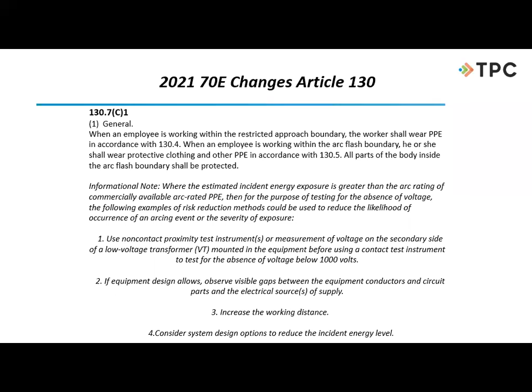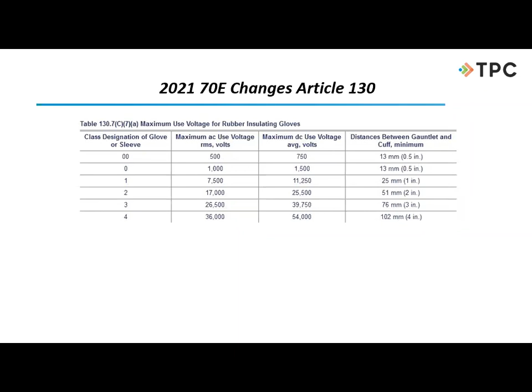They did revise our table on rubber gloves. They gave us, depending on the class of glove, whether it's a 00, 1, or 2, when you get up into medium voltage, the distance between the gauntlet and the cuff. So the rubber glove does have to extend a little bit beyond the leather protector. You can see a half inch for the lower classifications, and a little bit higher when we get up into those higher voltage levels.